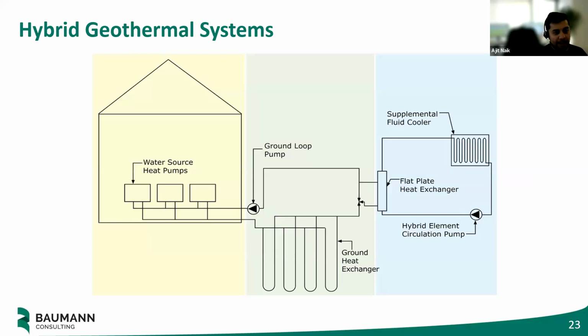In that previous example with more cooling than heating, we can design a vertical ground source geothermal system but add some supplemental cooling, like a backup fluid cooler or cooling tower that runs just for those hours when the water temperature in the hottest months gets a bit hotter than we'd like, bringing the temperature back down.